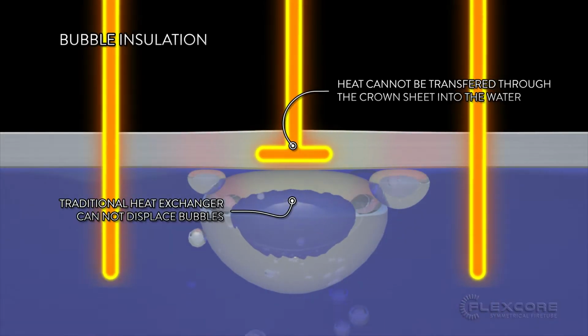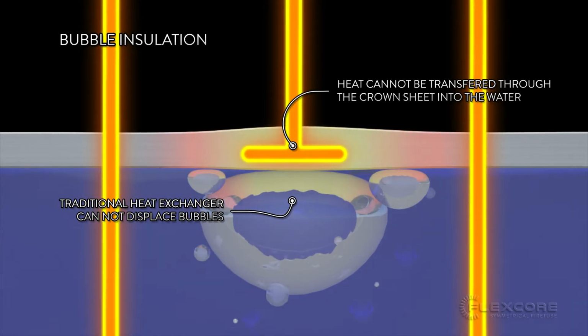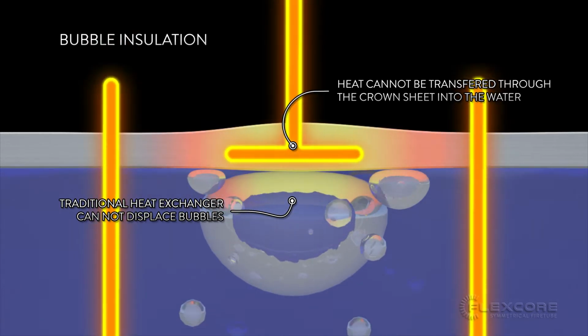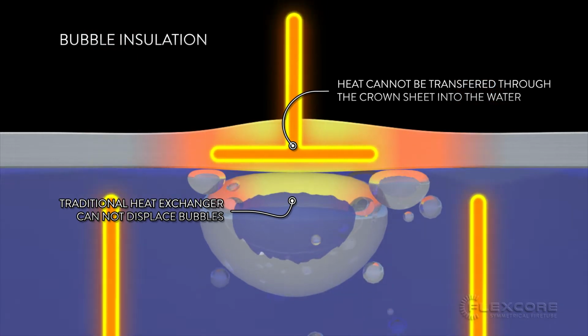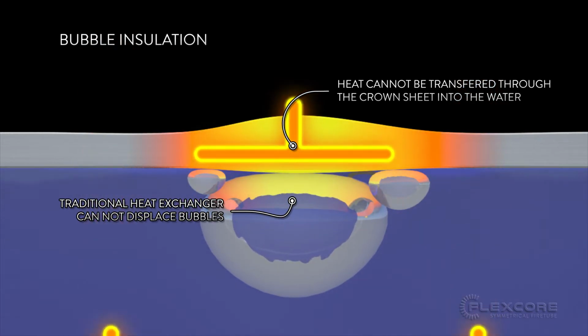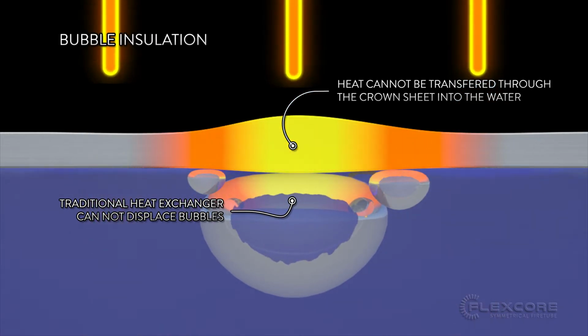Air bubbles sitting on the crown sheet will create a hotspot on that sheet. This is because the incoming heat is insulated by the bubbles and cannot be transferred to the water below, leaving only the metal to absorb the energy from the burner.